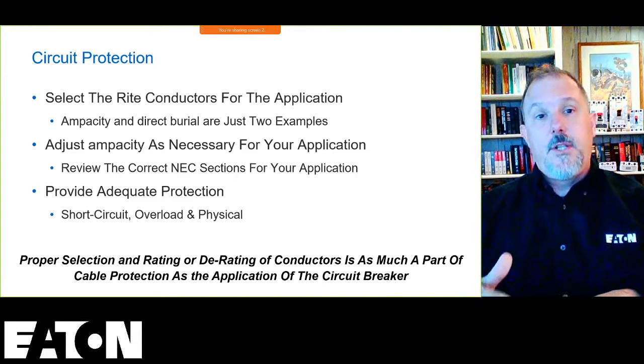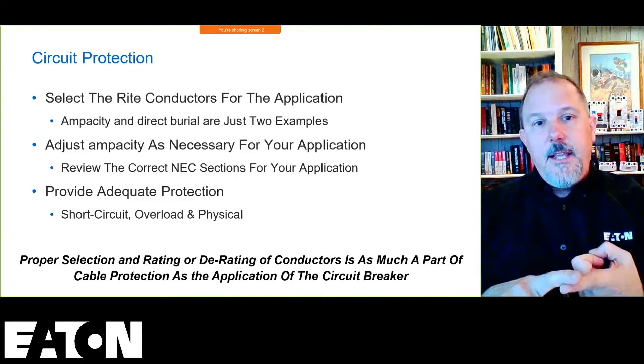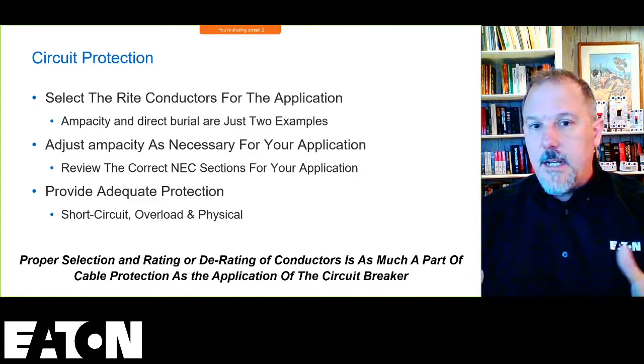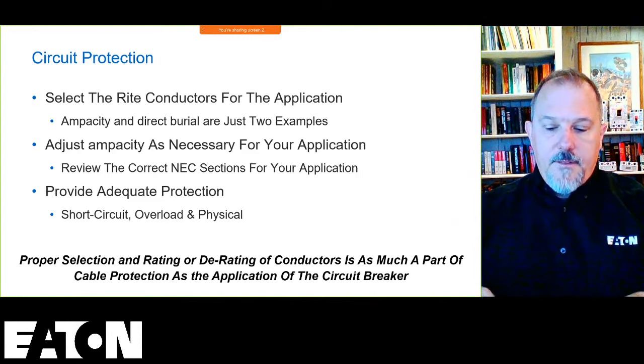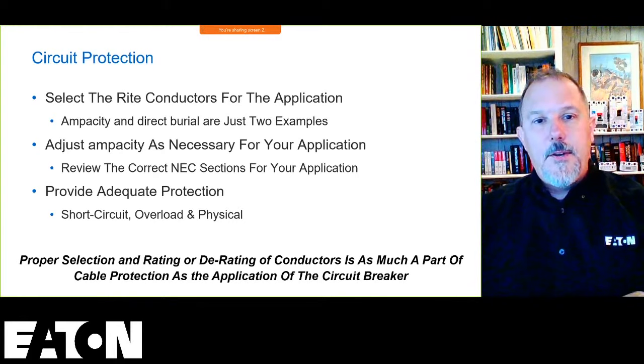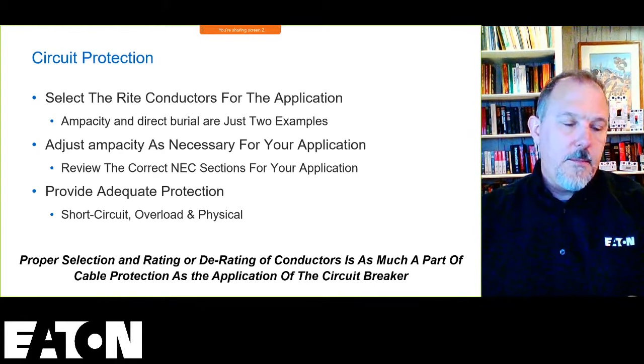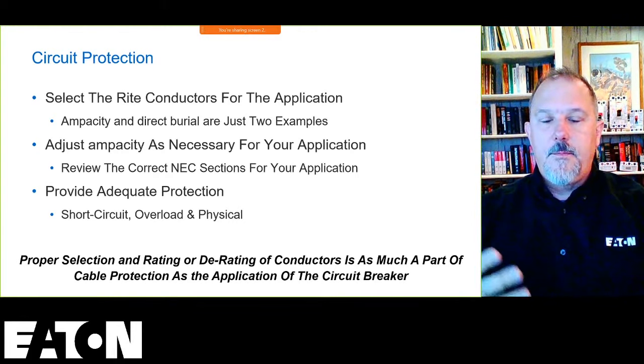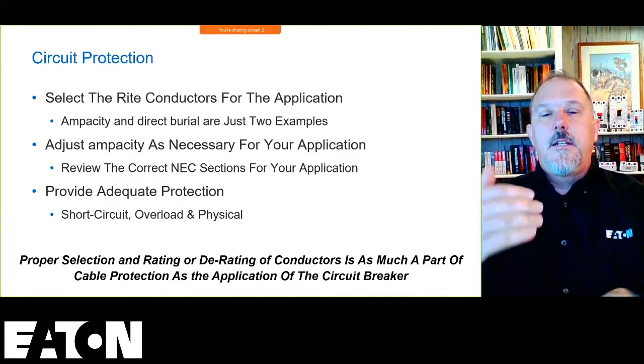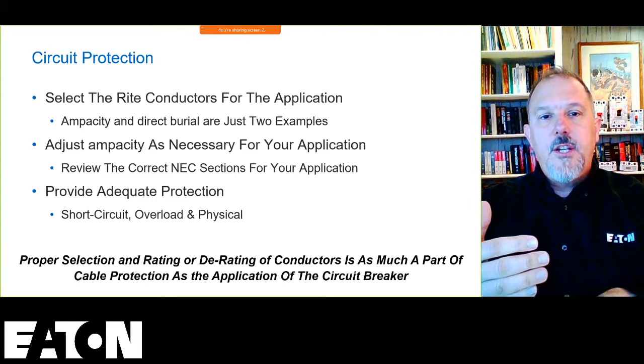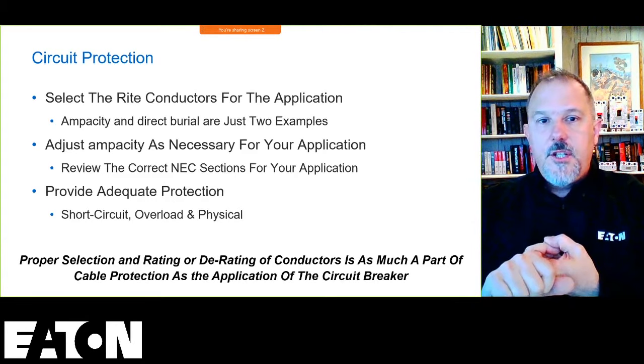We have to think not just about the ampacity, but about the environment that the conductor is going to be in. For example, is it going to be in a wet location, a damp location? Is it going to be protected in a raceway? Is it going to be exposed? You have to understand the conductor's application and make sure that you pick the right conductor for the job.